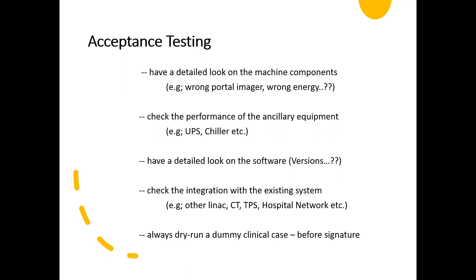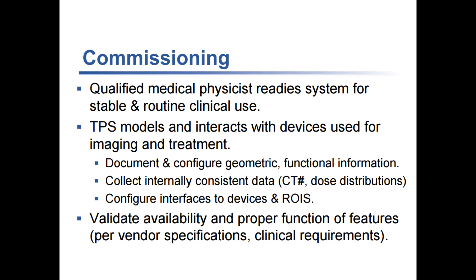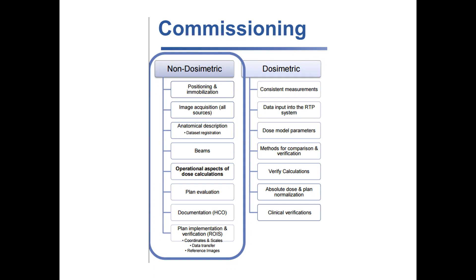So the commissioning phase, basically the clinical medical phase, is where the system is made stable for routine clinical use, and it validates the availability and the proper function of the features. We all know that. There are two types of commissioning, dosimetric and non-dosimetric. Dosimetric commissioning is everything we need for our treatment planning system and to do the patient calculation. The non-dosimetric things are the other things, for example, setting up patient immobilization devices and making certain policies, procedures and guidelines. All these come up in a non-dosimetric scenario. But certainly, in order to commence a clinical service, we need these non-dosimetric services as well, in addition to dosimetric services.